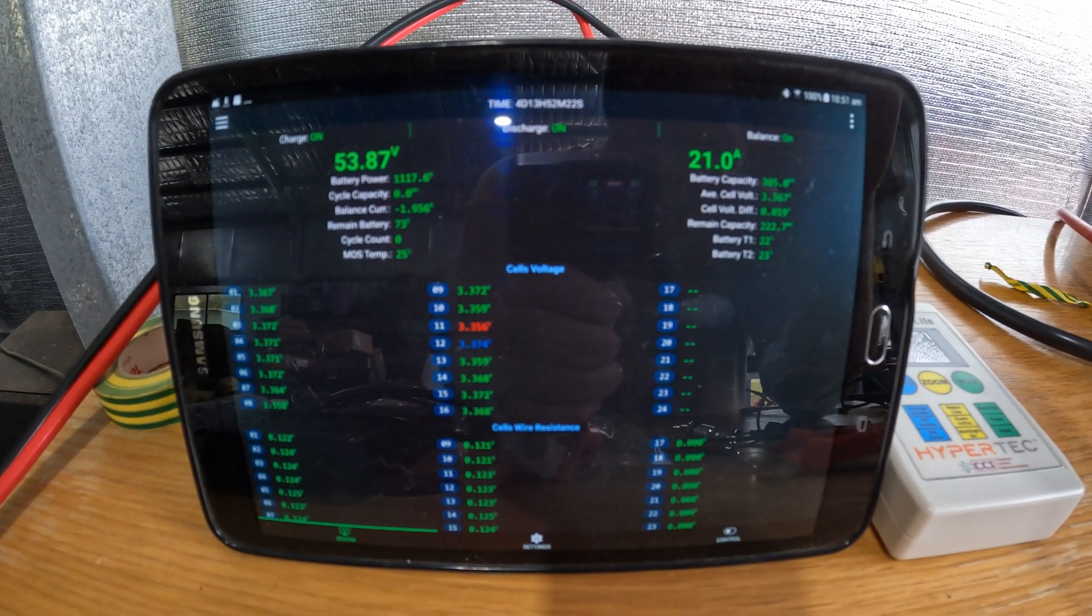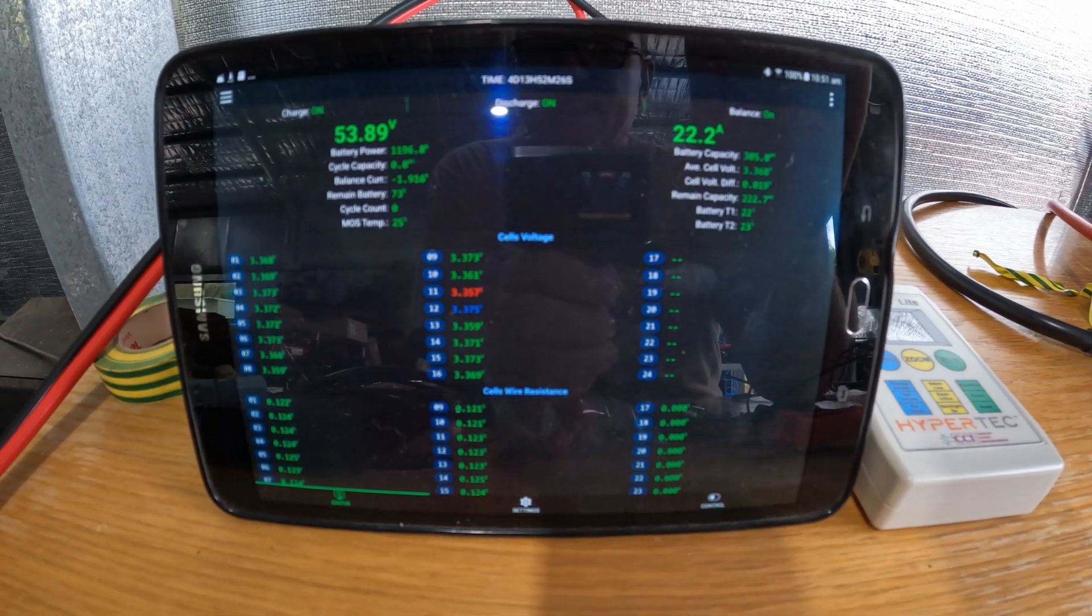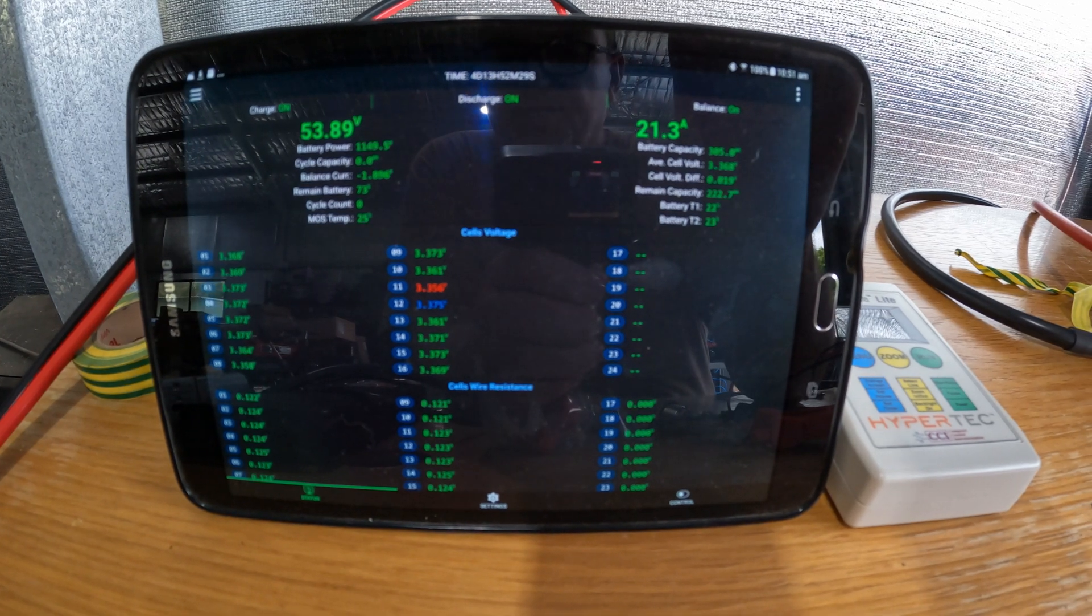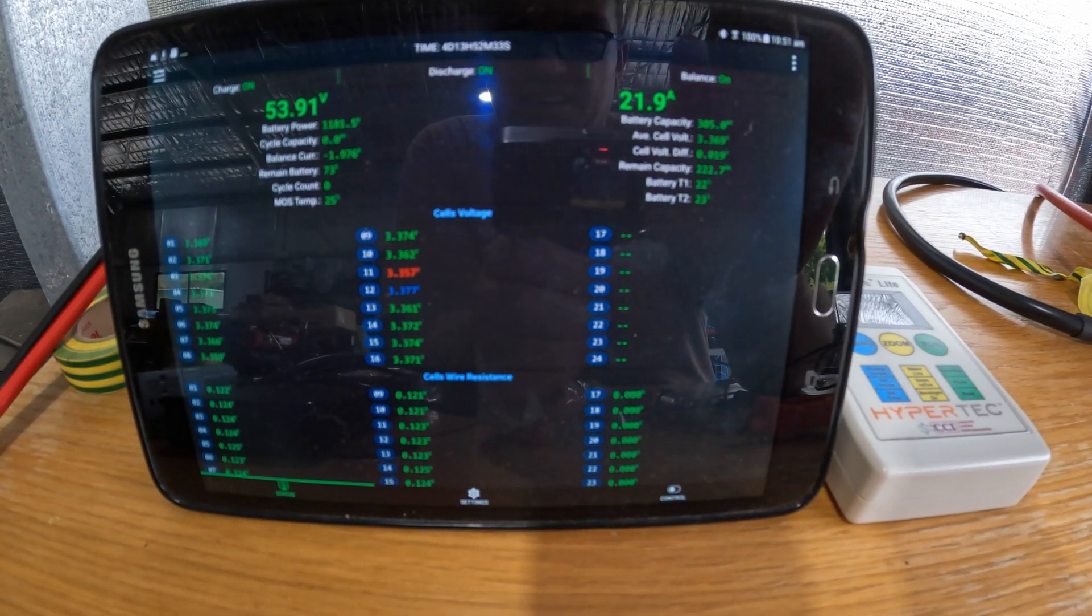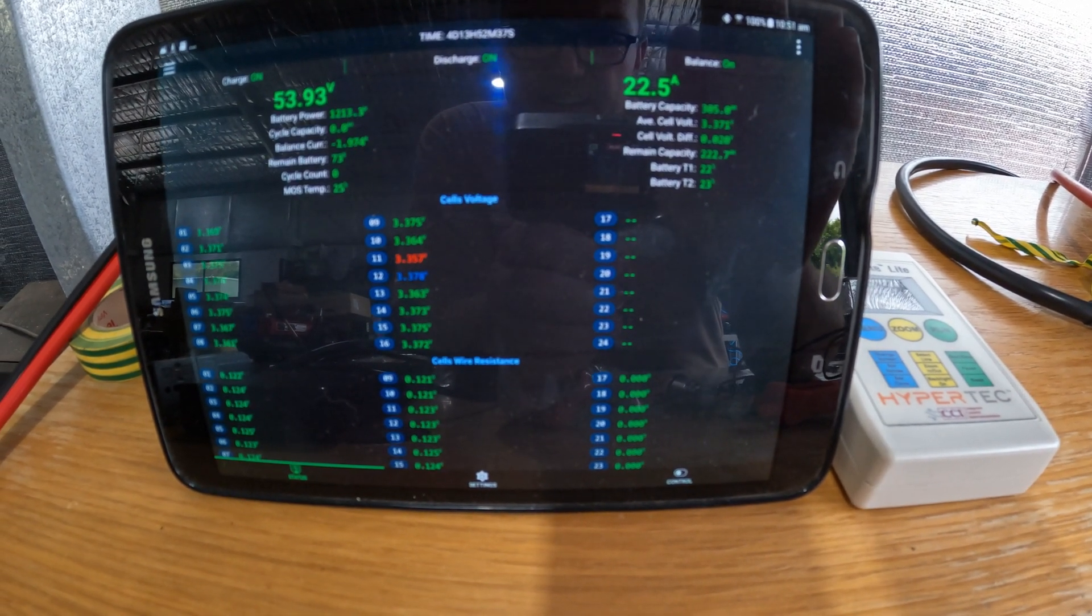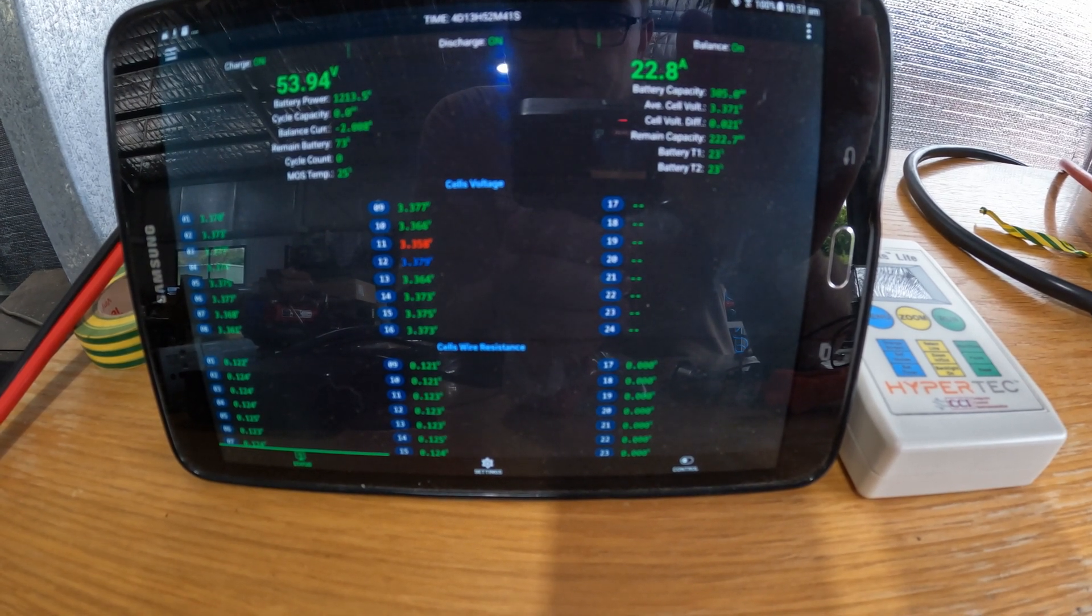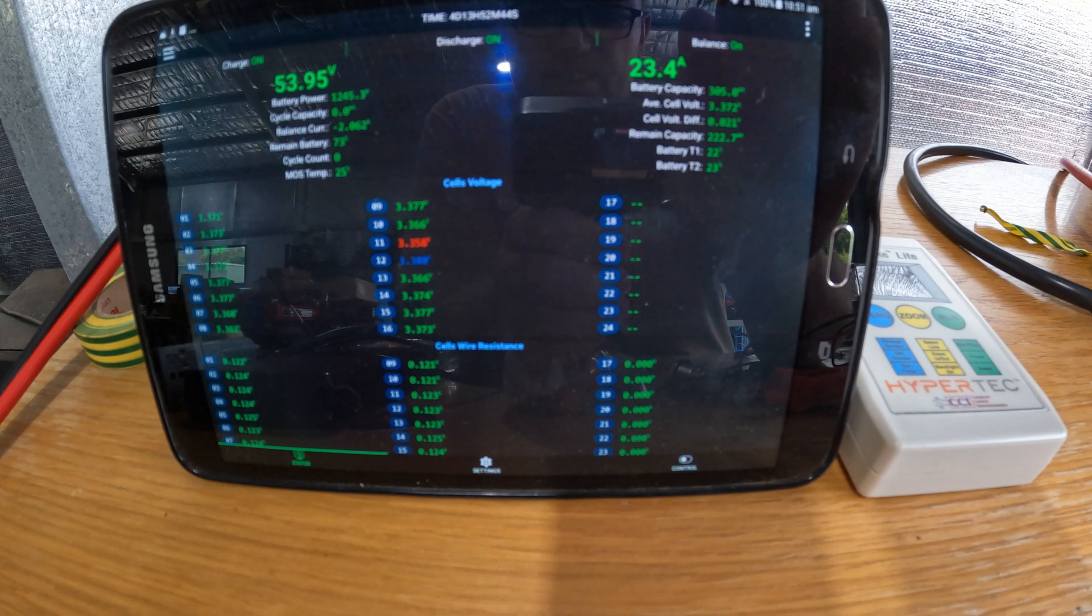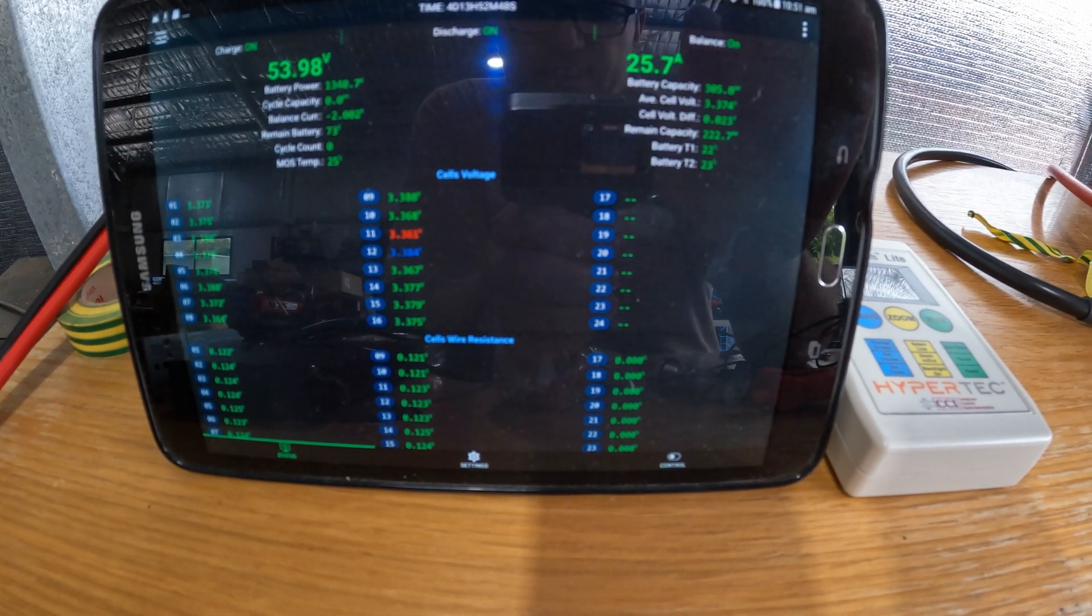We can see the same sort of charge going in. We can see 21 amps coming into the batteries. The batteries are virtually full, they're going to take a small amount of charge today but they are already at basically 100 percent. But that's fine, we will let it do what it needs to do, charge it up, give it a bit of a test run and let it all work itself out.